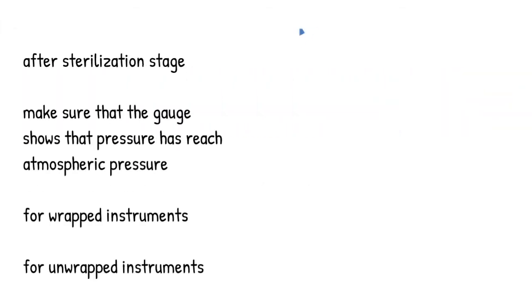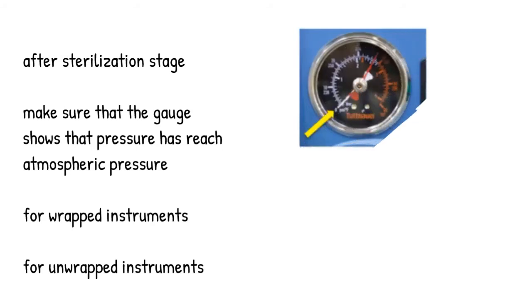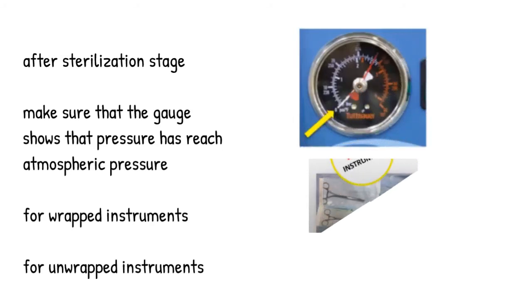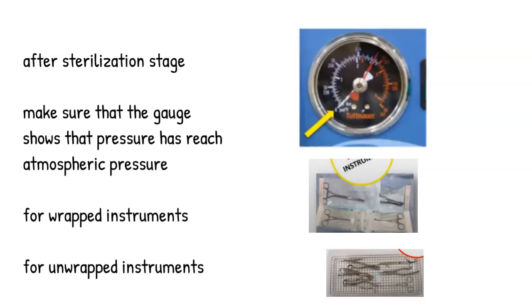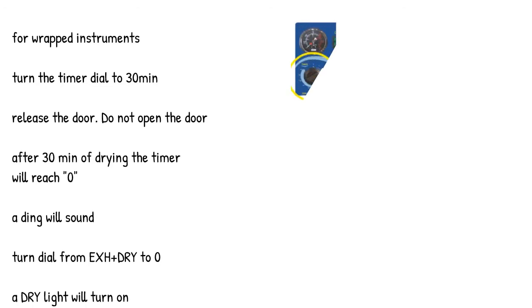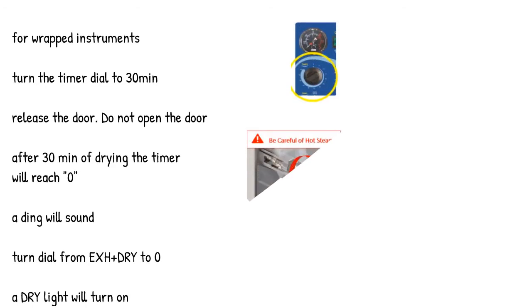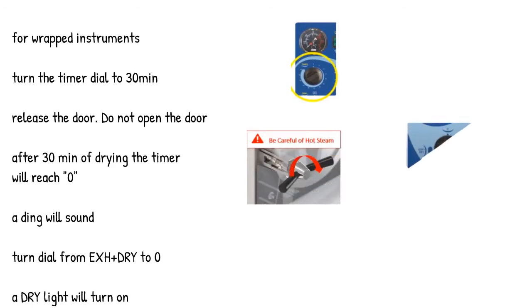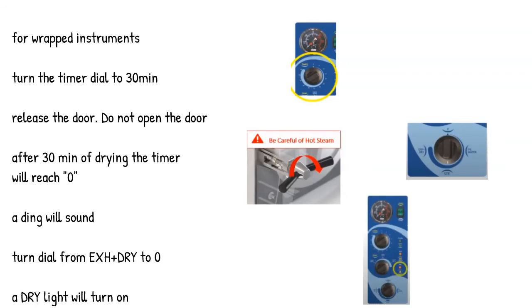After the sterilization stage, make sure that the gauge shows that pressure has reached atmospheric pressure. For wrapped instruments: turn the timer dial to 30 minutes. Release the door. Do not open the door. After 30 minutes of drying, the timer will reach 0. A ding will sound. Turn the dial from EXH plus dry to 0. The dry light will turn on.